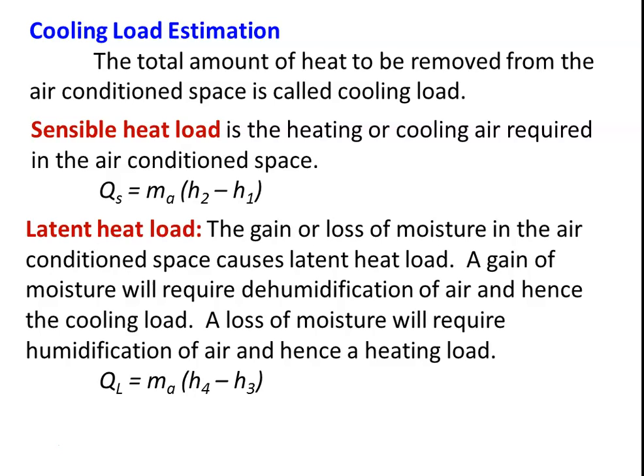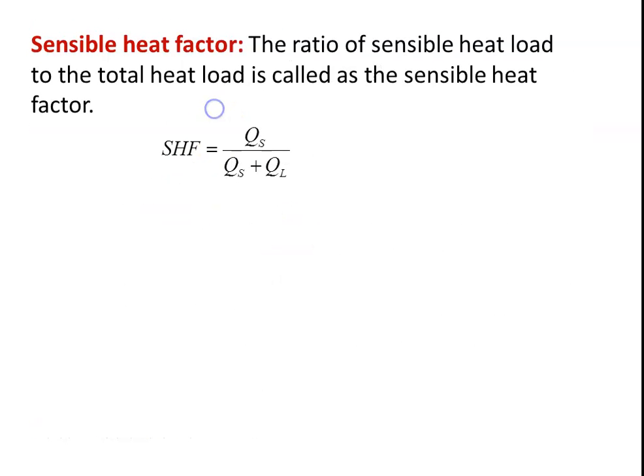So the latent heat load equals MA into H4 minus H3. H4 is the final enthalpy after humidification or dehumidification, and H3 is the enthalpy before the process. MA is the mass of the air. And the total heat load equals QS plus QL, the sensible heat load plus the latent heat load. Sensible heat factor is one parameter for the design of air conditioning systems. Sensible heat factor equals the ratio of sensible heat load to the total heat load. So QS divided by QS plus QL. This is the sensible heat factor.